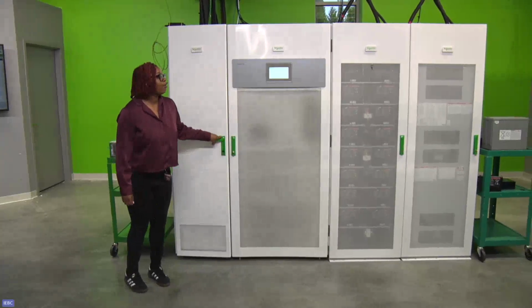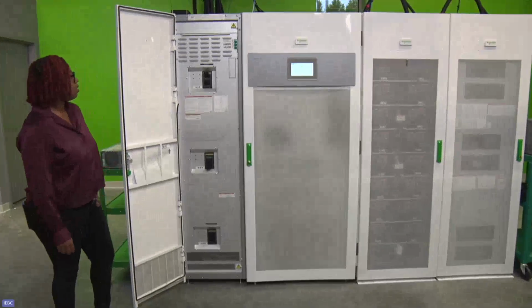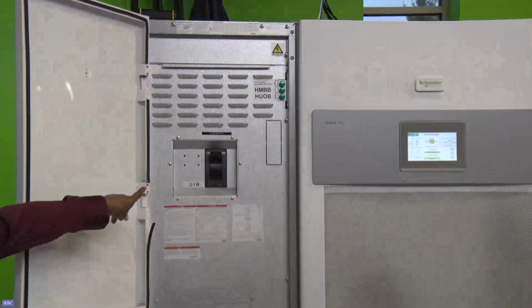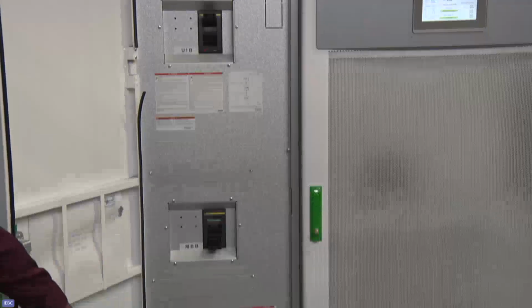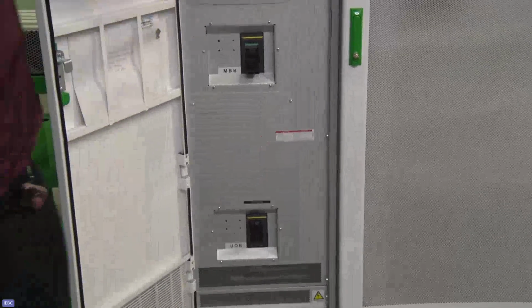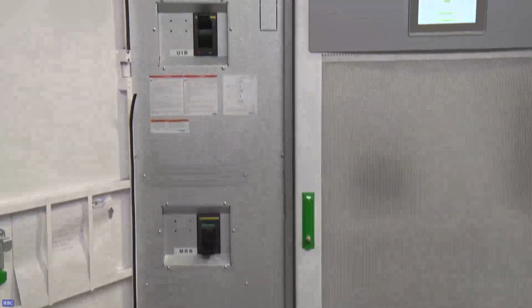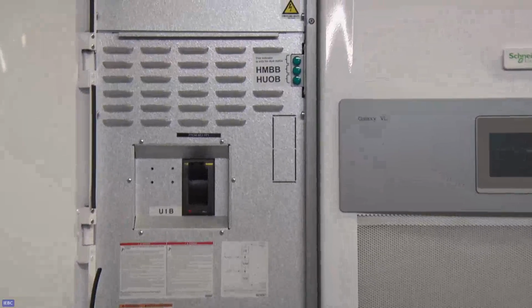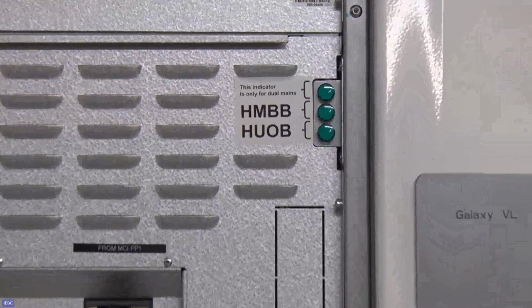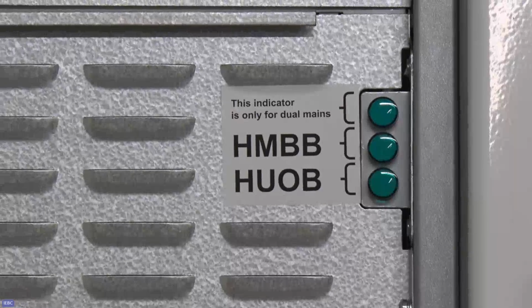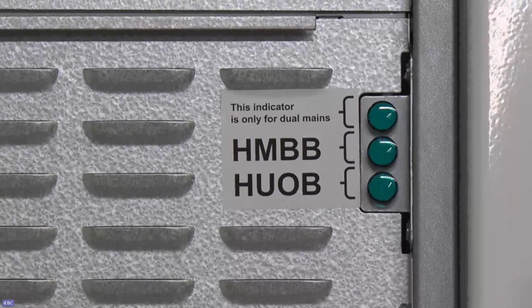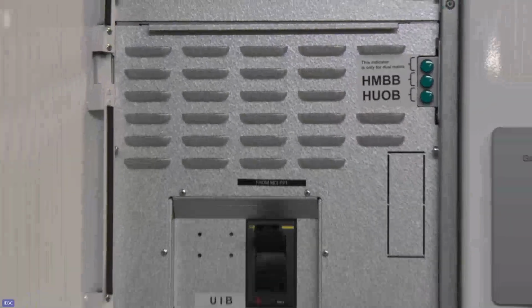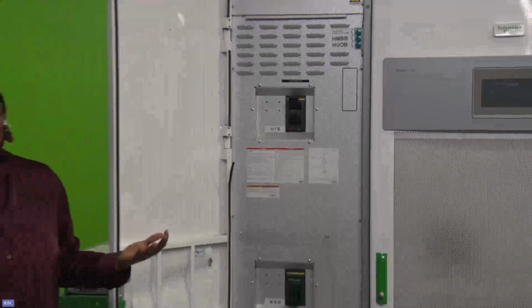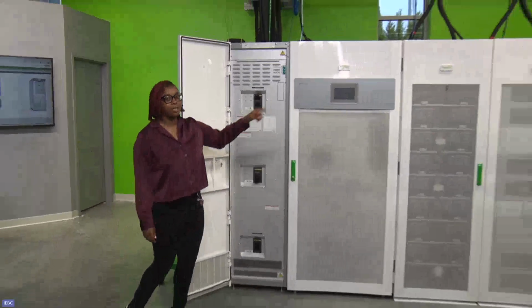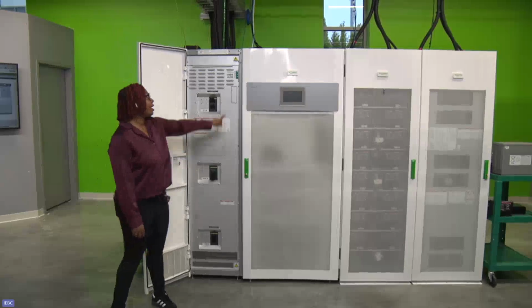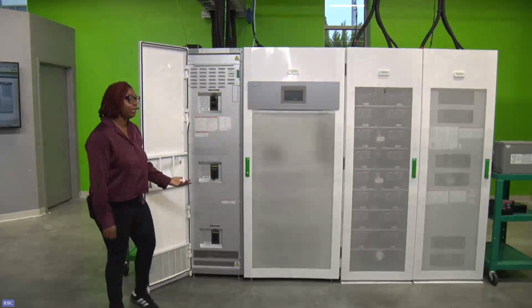Next to it, we have our maintenance bypass cabinet. Here we have 3 breakers: our UPS input breaker, maintenance bypass breaker, and our UPS output breaker. We also have these LED indicators here, which are very helpful when it comes to powering up and shutting down this UPS system. This UPS is meant to be set in place and forgotten about. So in the times that you may need to turn it off or on, you may forget, and this will actually give you guided sequences and guide you directly through it with these LED indicators.